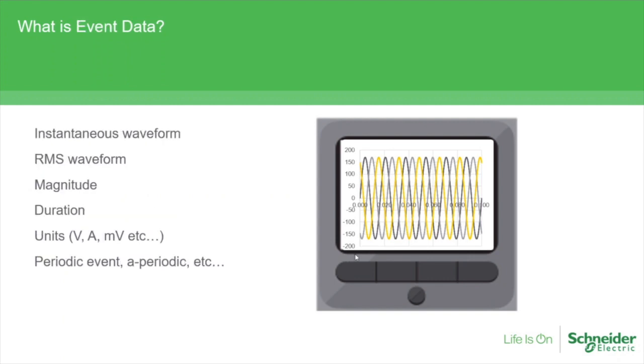So then when we get into event data, we're usually looking at the waveform, if it's supported by the meter. The waveform can provide a lot of information, not just the sampling rates but, based on what's recorded, you can identify the type of event, whether it's a swell, a transient, if harmonics are an issue, or if there was an interruption. The RMS waveform is more or less looking at the RMS values over time. It's not a sinusoidal waveform. But then you also want the magnitude and duration of events.